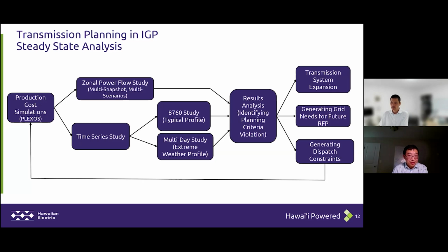So in the steady state part, basically this slide shows the high-level process of how we do steady state analysis. We still keep doing the snapshot power flow study, which addresses traditional scenarios like peak load condition or min load condition. We also look into those plants or groups of plants' deliverability. Basically, we need to make sure that the plant can deliver their contract capacity when the system needs them most. So we address those using multiple snapshots, multiple scenarios, zonal type power flow study.